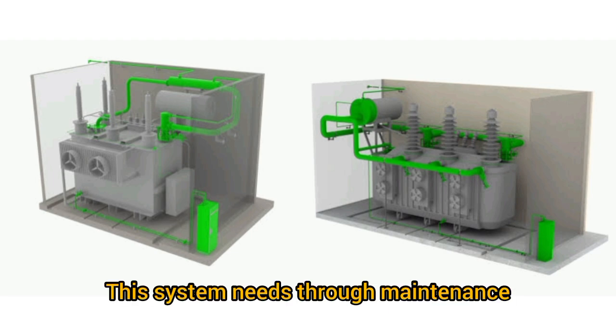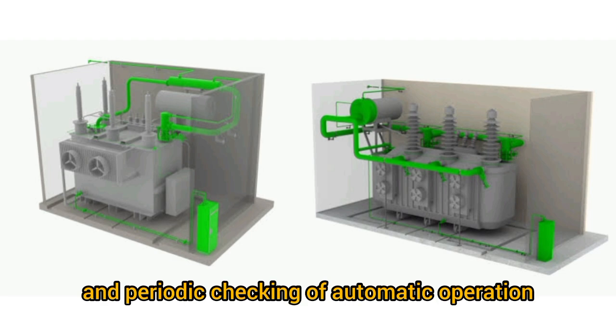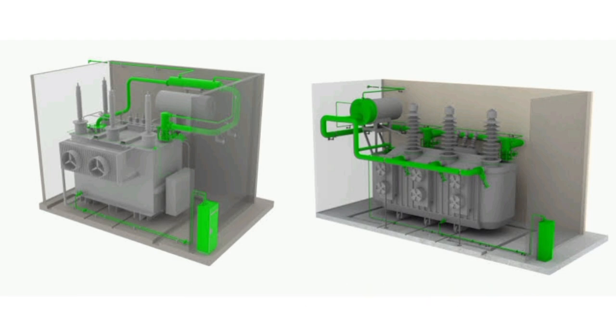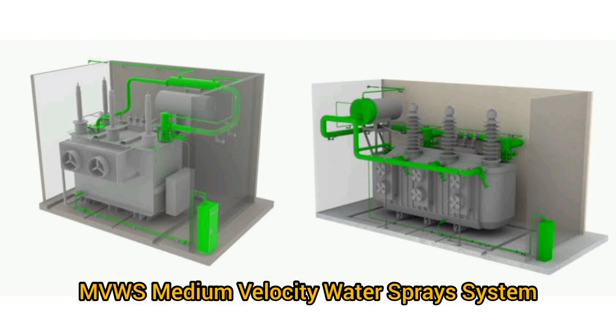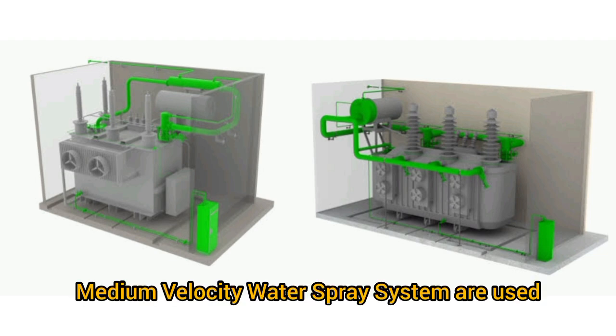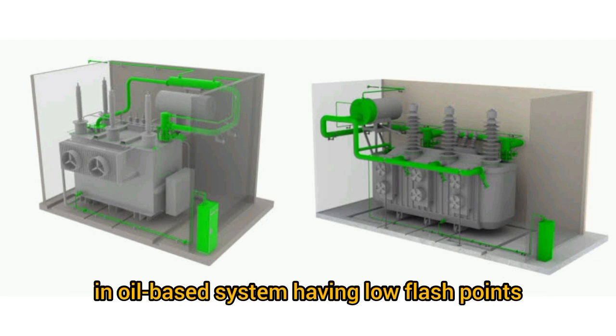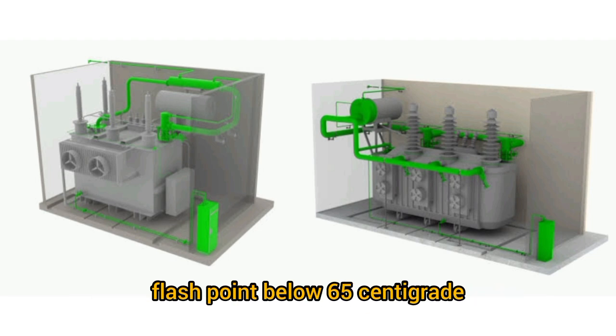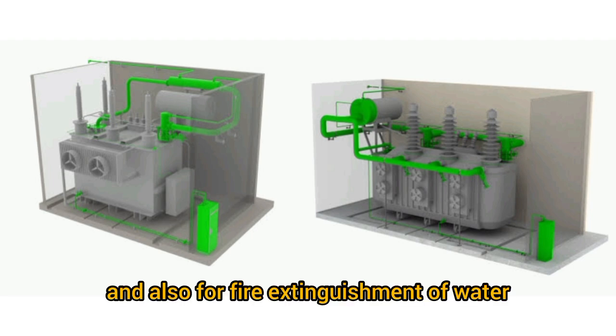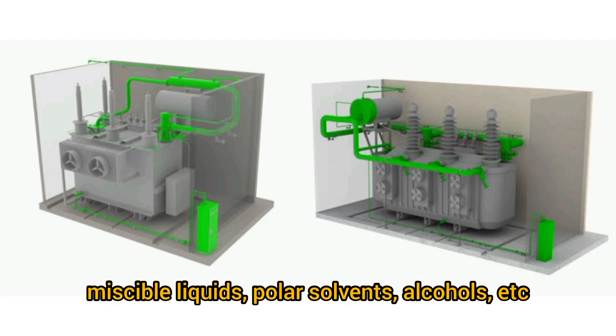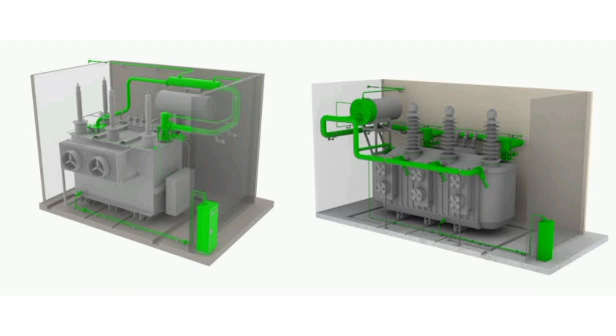This system needs thorough maintenance and periodic checking of automatic operation for reliability during fire. MVWS, Medium Velocity Water Sprays System. Medium velocity water spray systems are used in oil-based systems having low flash points, flash point below 65 centigrade, and also for fire extinguishment of water miscible liquids, polar solvents, alcohols, etc.